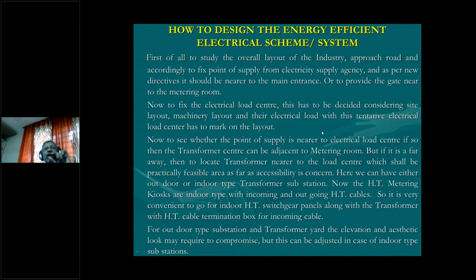If you can work out the electrical load center, try to provide your distribution transformer there, so automatically your distribution cost will be reduced. One thing I would like to mention: all our losses are I square R, always related to current. If you consider an 11 kV network, for 1000 kVA the current at 11 kV is 52.5 ampere. For 22 kV, it is 26.25 ampere. For 33 kV, it is 17.5 ampere. But at 415 volt, that is the LT side, for 1000 kVA the current will be 1390 ampere.